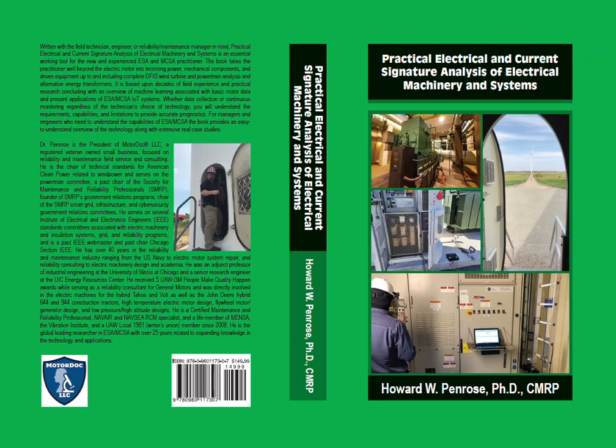They did see a one-time RPM frequency in vibration analysis, but had not looked at the number of fields times RPM of the motor, nor the number of amortisseur winding bars times running speed. I suggested they had bad rotor field coils and was told the motor had just gone through a repair process and nothing was found.